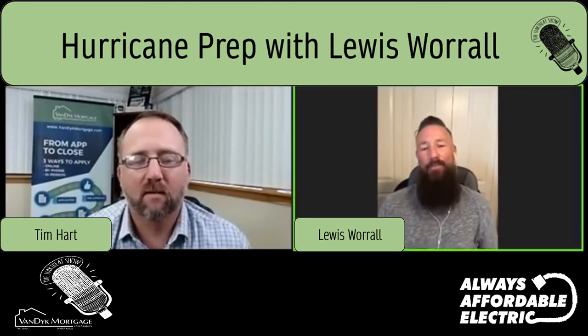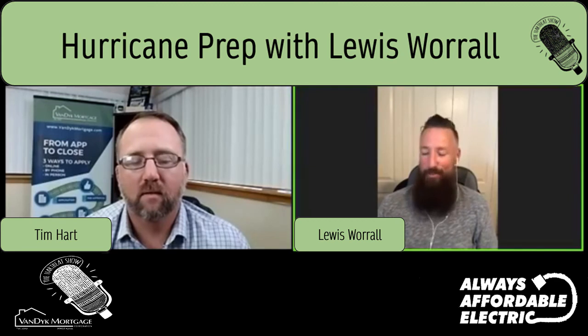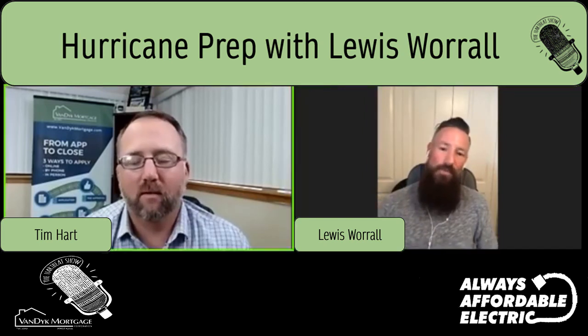That's what people do: they make a cord with a male end that goes into your generator and a male end that goes into, say, your dryer or your range or somewhere in your house that will backfeed the house. The only problem is if that cord comes out of the wall, it's pretty much a 240 volt taser just bouncing around wherever it is.